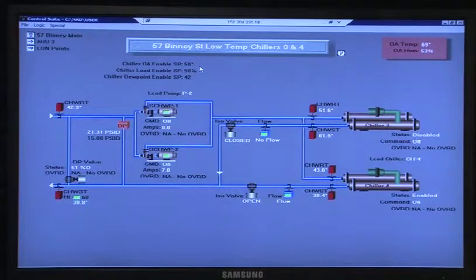When you have high humidity, you're trying to control humidity. You're not going to do it unless you get that chilled water coil down and strip that moisture out, send it down to the 7th floor, and get the reheats to reheat that air. This is when we have those beautiful design days where we get calls from the pharmacy saying it's 70 degree dew point down here. What's going on with you guys? Well, the only way we can control that dew point is by a low temp chiller delivering 40 something degrees off that chiller discharge, sending that cold air, stripping it down to 100% saturation point right off the face of the coil, sending that air down. So the dew point now is at 40 something degrees, and then as soon as you send it down there and you engage reheat within the pharmacy space, which it will do, because of the amount of airflow down there.